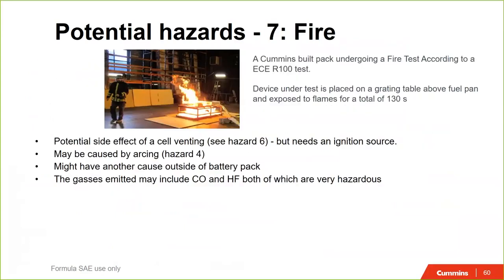Fire is the next thing we talk about here. For automotive packs, in Europe, you have to undergo a fire test under ECE Reg 100. This involves placing the pack over a roaring flame for 130 seconds. Why 130 seconds is because 2 minutes is considered a standard egress time from a crashed or damaged vehicle. And the extra 10 seconds, I think, was because it was formed by a committee.